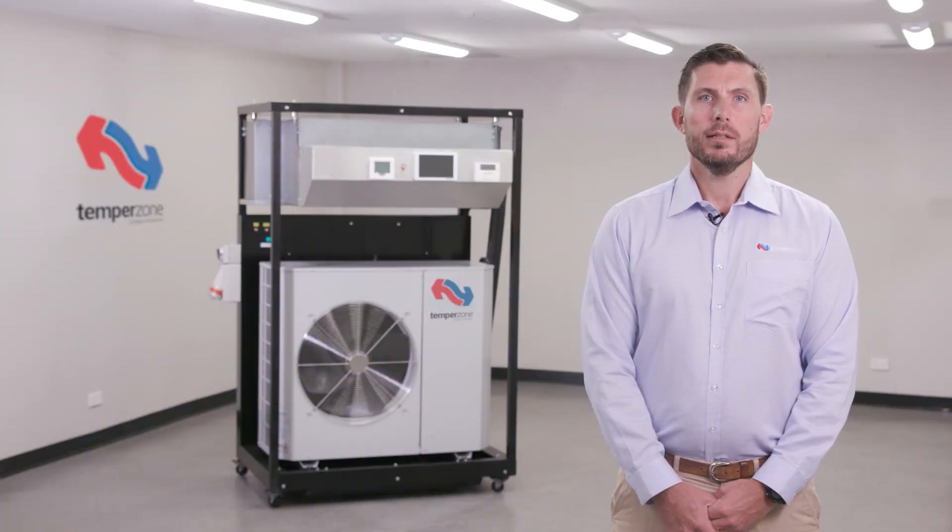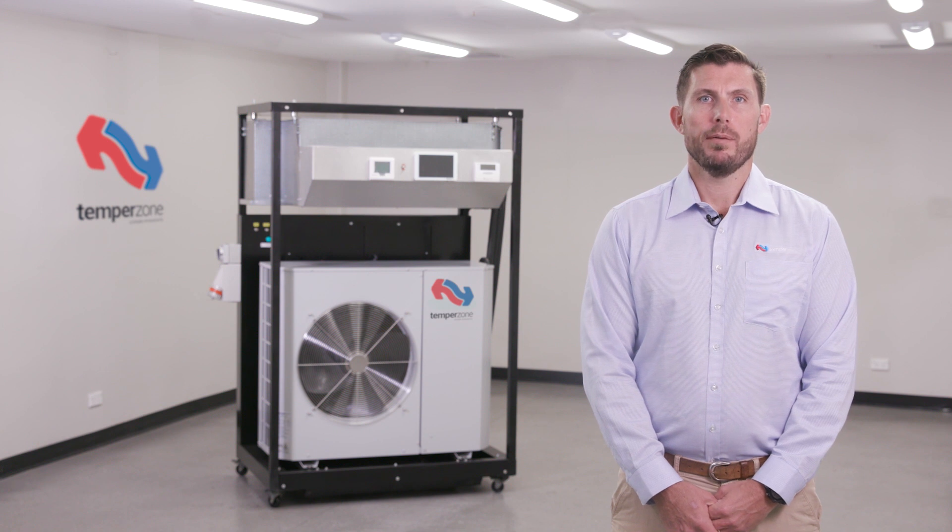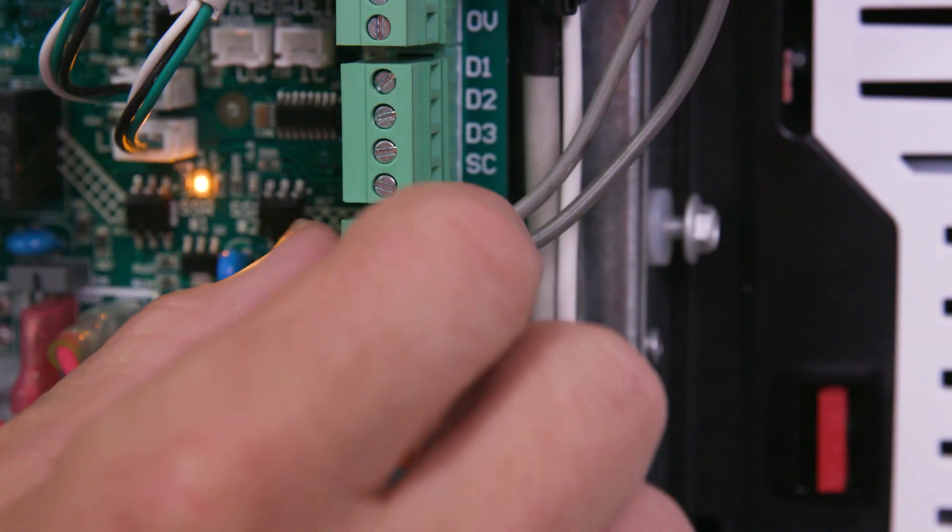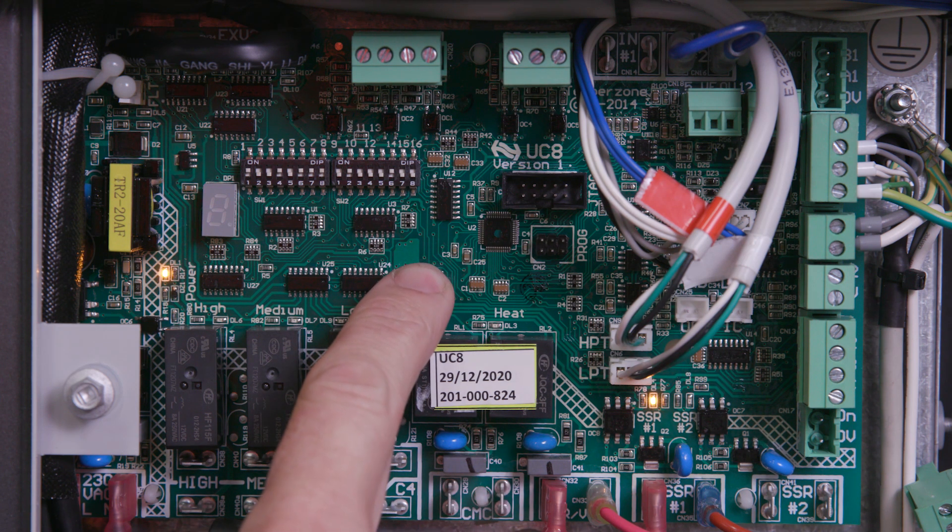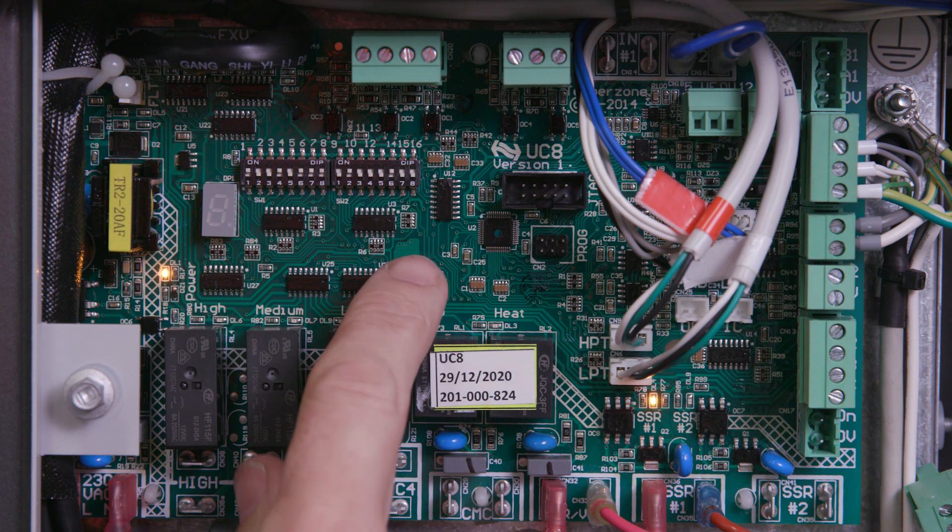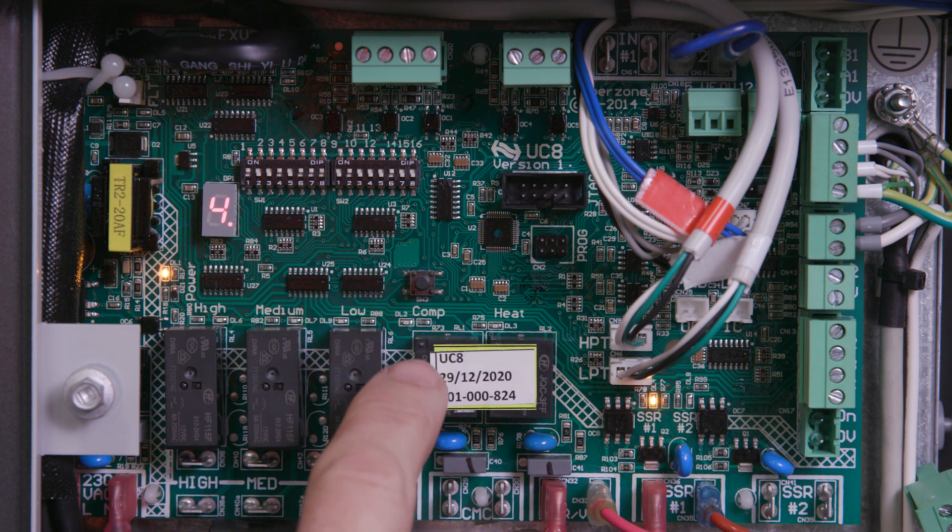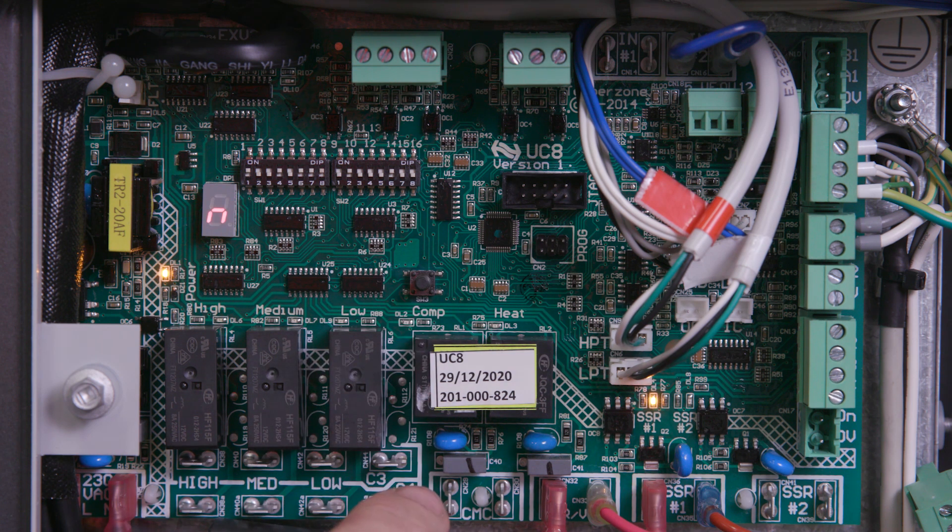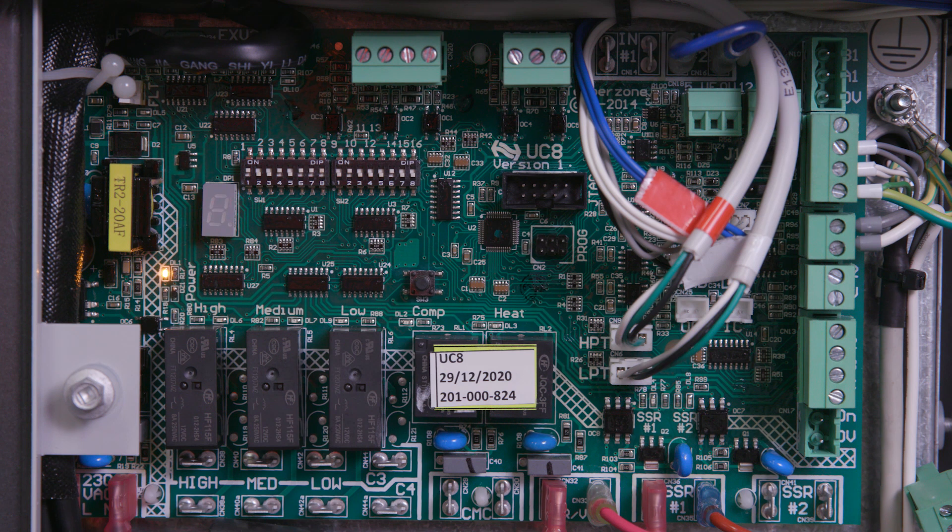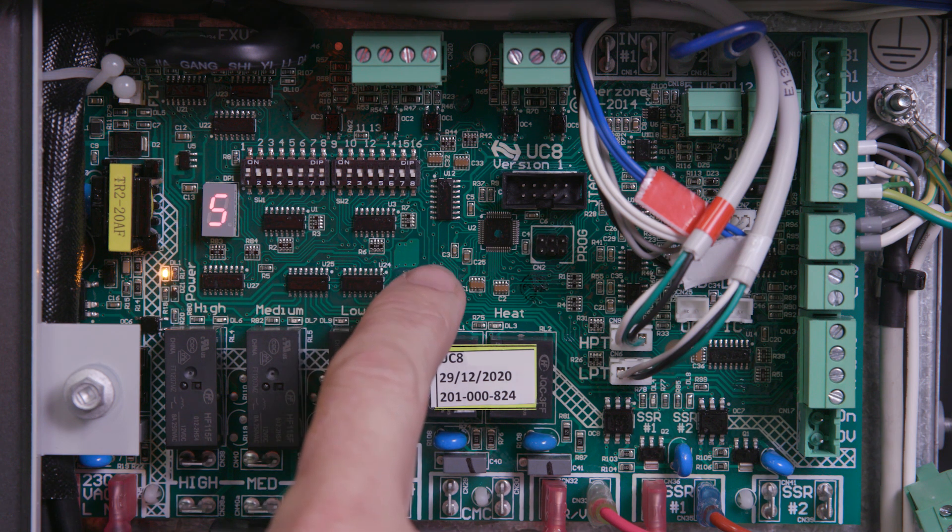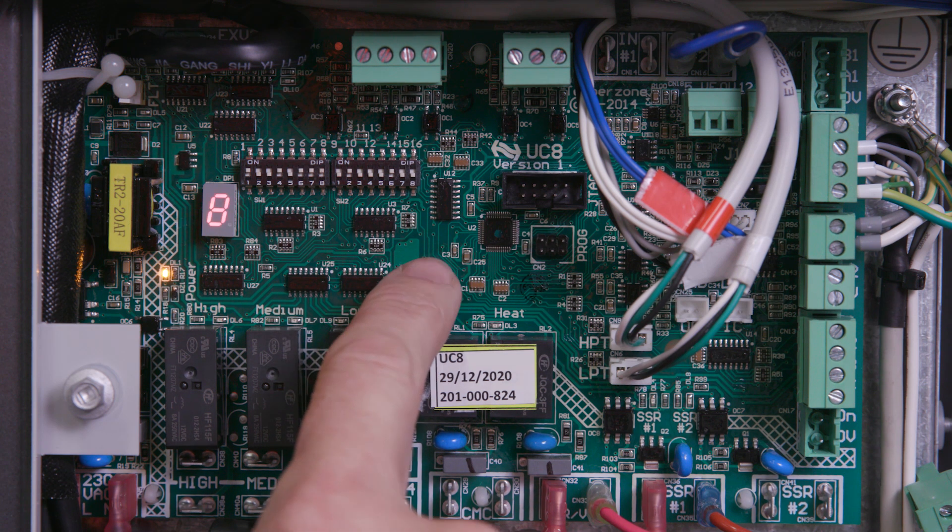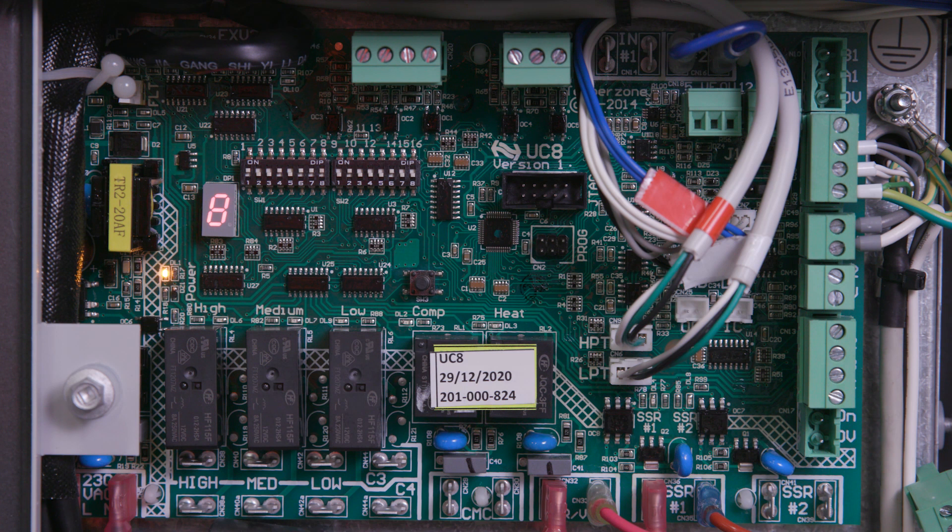To enter the special modes for version 6.1.4 and preceding current software versions, a four page menu is used. First remove the remote on-off terminal. Press and hold the SW3 push button for two seconds until the UC8 displays 0 and release. Use short presses to select the desired menu page. Press and hold for selection of desired menu page. Use short presses to select the desired special mode, then press and hold to enter and save. The UC8 will now return to normal operation with the setting saved.